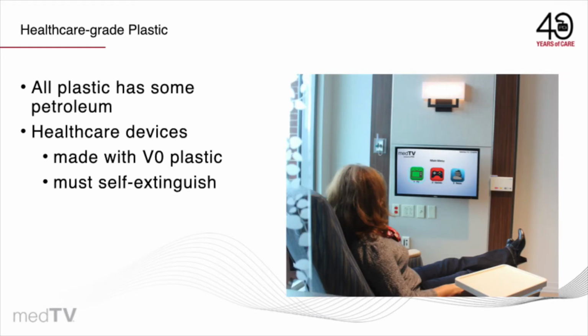Also, all plastics have some degree of petroleum in them when they're made. In the healthcare industry, it has to be made with V0 plastic, meaning that the product can be ignited with a flame, but if that flame is removed, it must self-extinguish. We all know that if you catch plastic on fire, it gives off some very noxious black smoke, and it can quickly cause a facility to have to be evacuated. So at any time it's lit or ignited, when you remove the flame, it must self-extinguish. That's another requirement for healthcare.